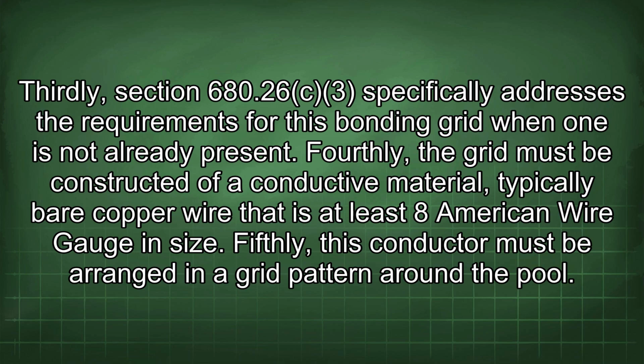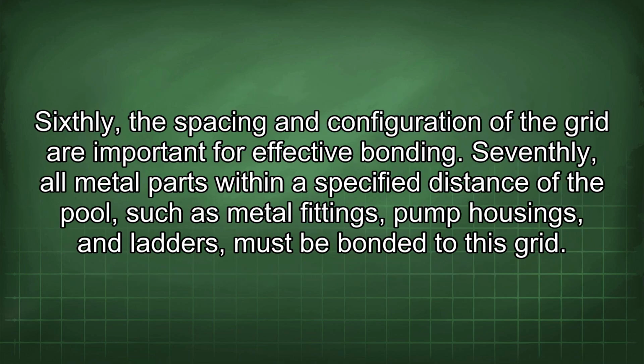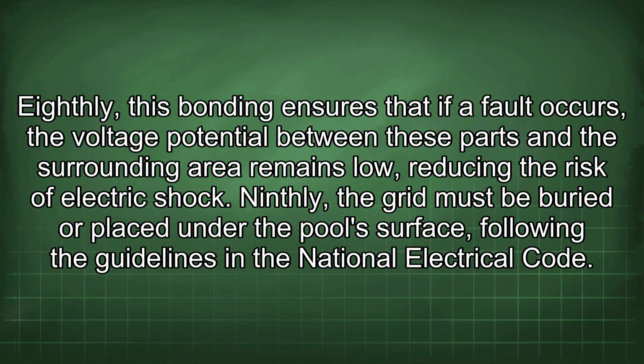Fourthly, the grid must be constructed of a conductive material, typically bare copper wire that is at least 8 American wire gauge in size. Fifthly, this conductor must be arranged in a grid pattern around the pool. Sixthly, the spacing and configuration of the grid are important for effective bonding. Seventhly, all metal parts within a specified distance of the pool, such as metal fittings, pump housings, and ladders, must be bonded to this grid. Eighthly, this bonding ensures that if a fault occurs, the voltage potential between these parts and the surrounding area remains low, reducing the risk of electric shock.